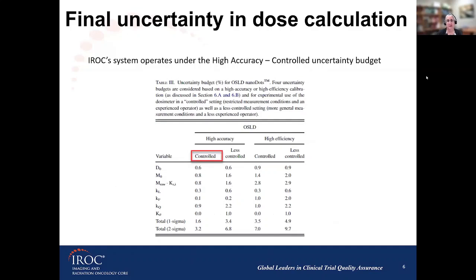With that said, and based on the assumptions you might be making or how you define this correction factor, Task Group 191 proposed 4 different levels in the final uncertainty for those calculations. IROC has what is called a high accuracy and control scenario that is able to provide a final uncertainty in dose at the level of 3.2% at 2 sigma.